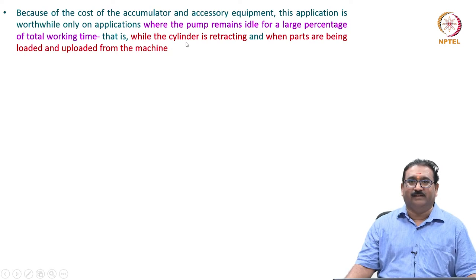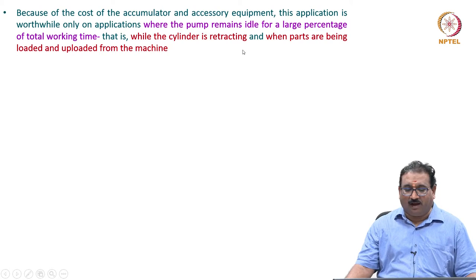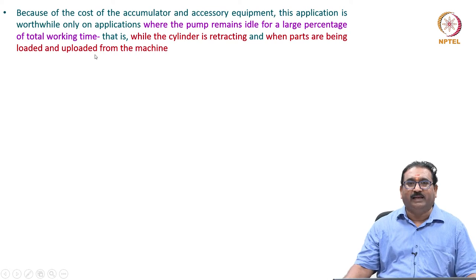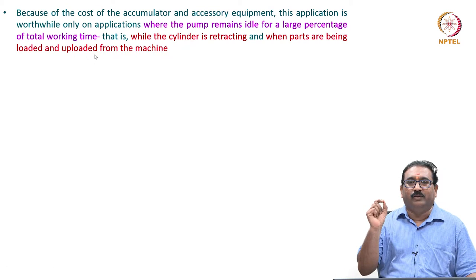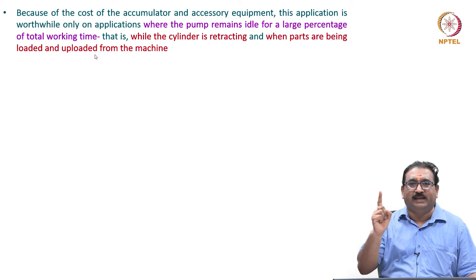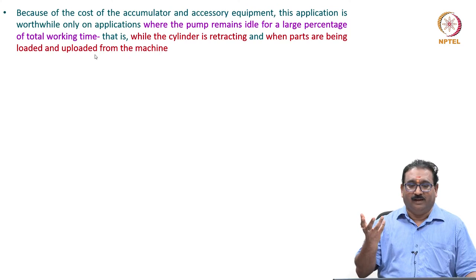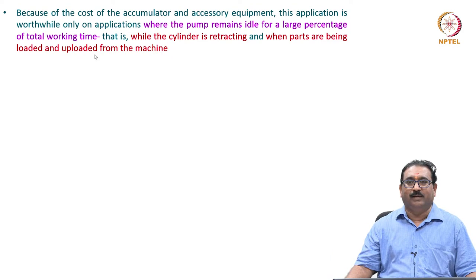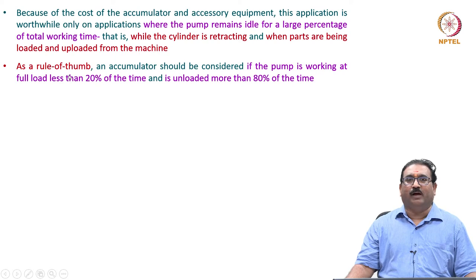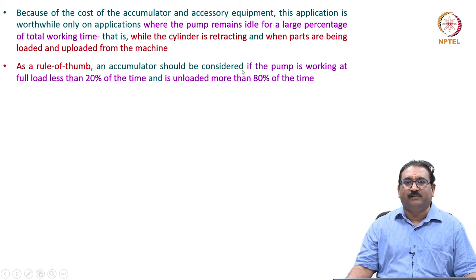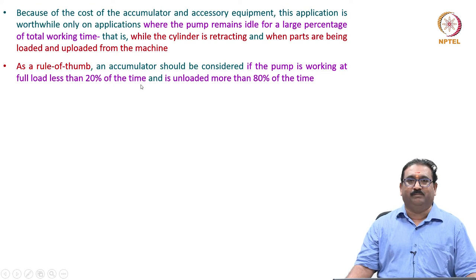That is, while the cylinder is retracting and when parts are being loaded and unloaded from the machine, no actual work is going on. As a rule of thumb, an accumulator should be considered if the pump is working at full load less than 20 percent of the time and is unloaded more than 80 percent of the time.